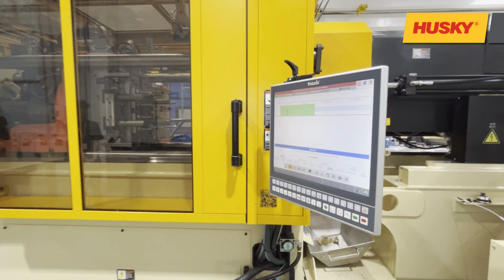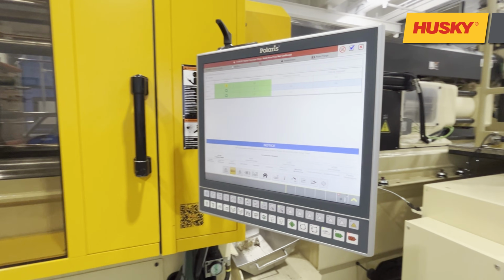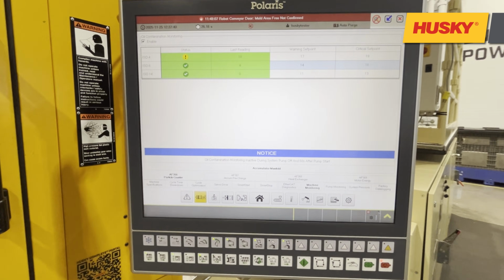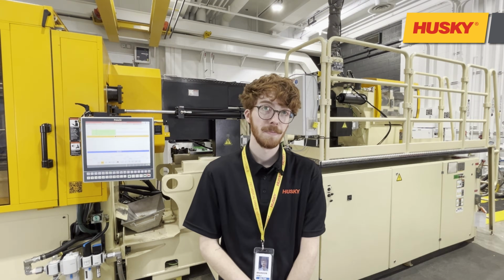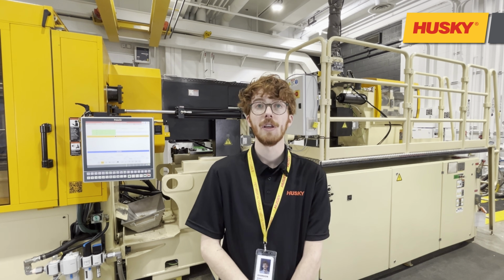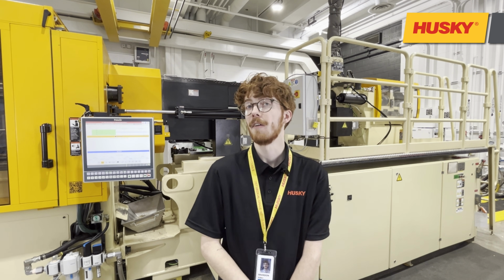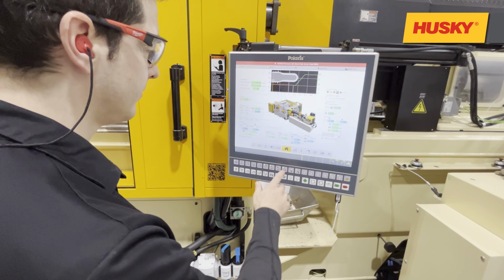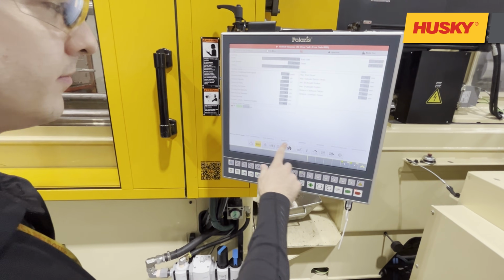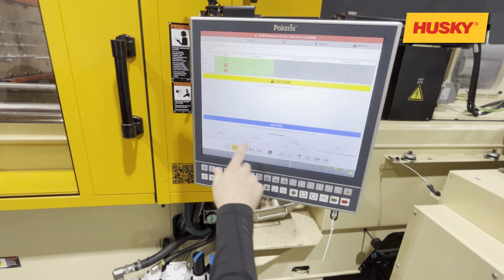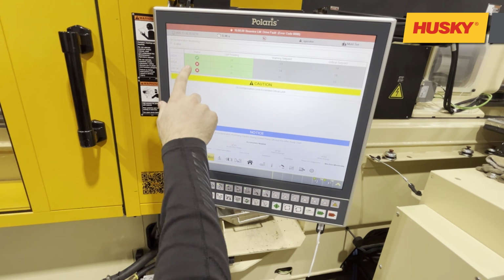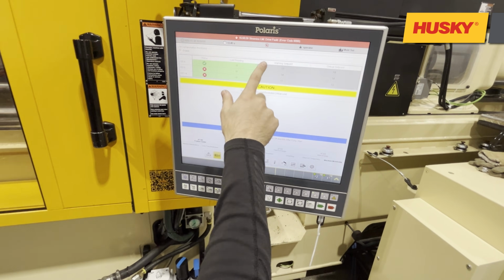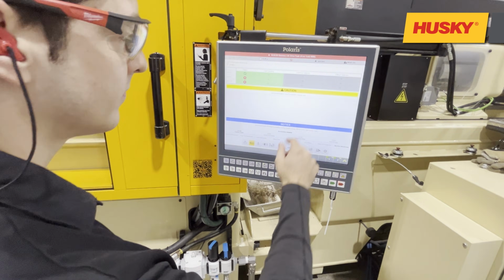Contamination levels are displayed on the HMI according to ISO 4406 standards. Here's how it works. Once the pump starts, we allow the lines to flush for 1 minute. After that, the particle counter begins testing, and every 5 minutes, ISO counts are reported straight to the HMI. This gives real-time insight into oil cleanliness and allows us to trend results, detecting issues before they take down the machine.